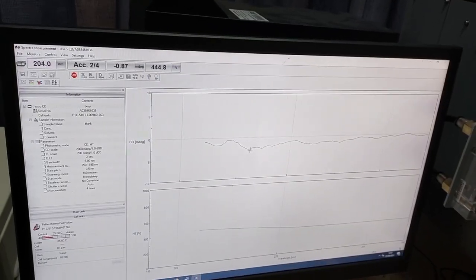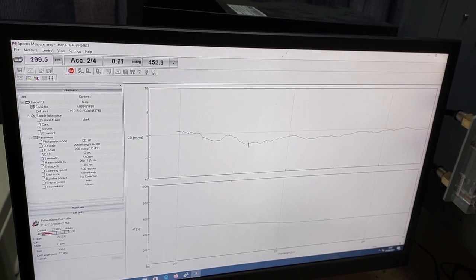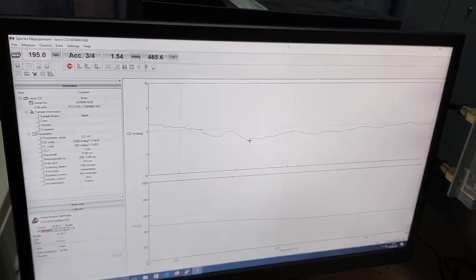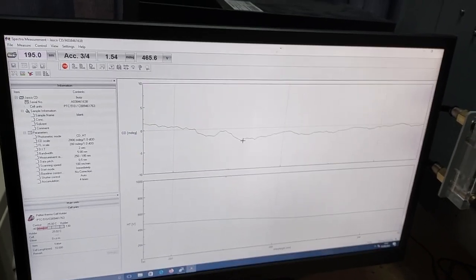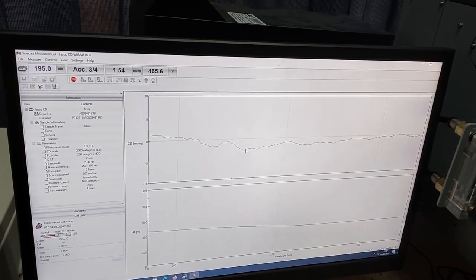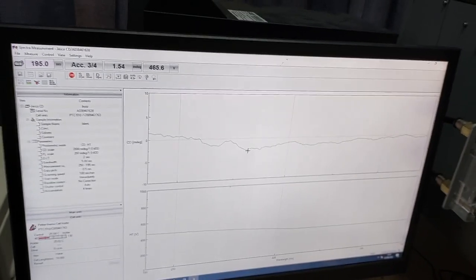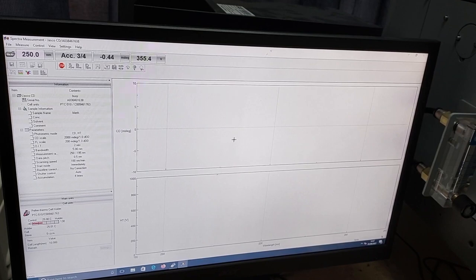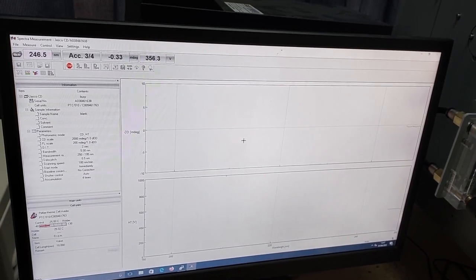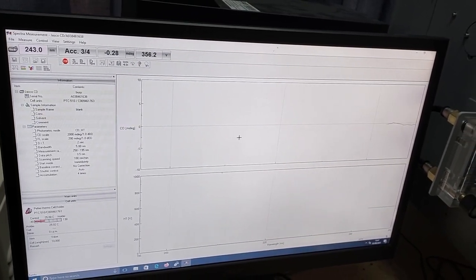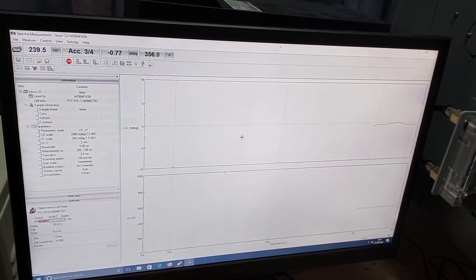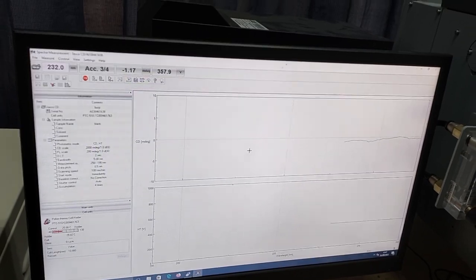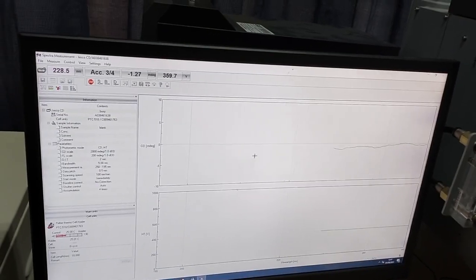As the sample absorbs photons, fewer photons will reach the detector. So a higher voltage is applied to the detector to get more secondary electrons by the PMT. Essentially, your light gets extinguished by your sample and a higher voltage is applied. When the absorbance of the sample becomes too high, very few photons reach the detector. Because very few electrons reach the detector, a higher voltage is applied to amplify the signal, and this is where the problem is. A very high voltage is applied when there are very few electrons.